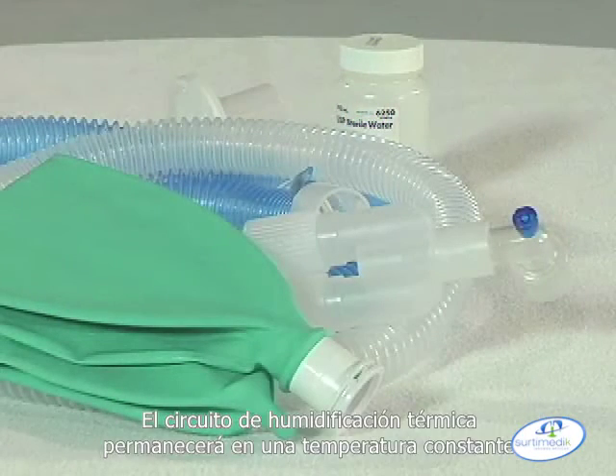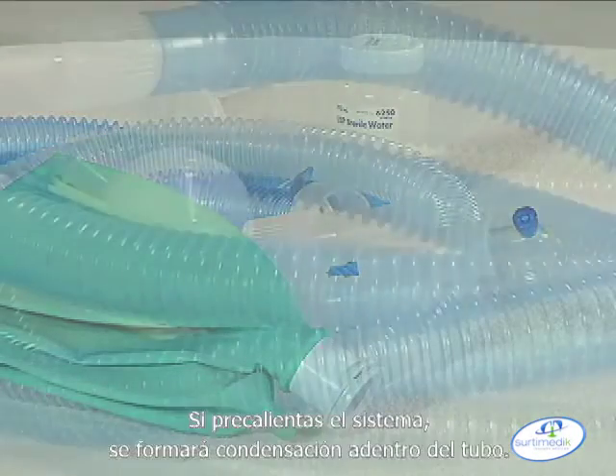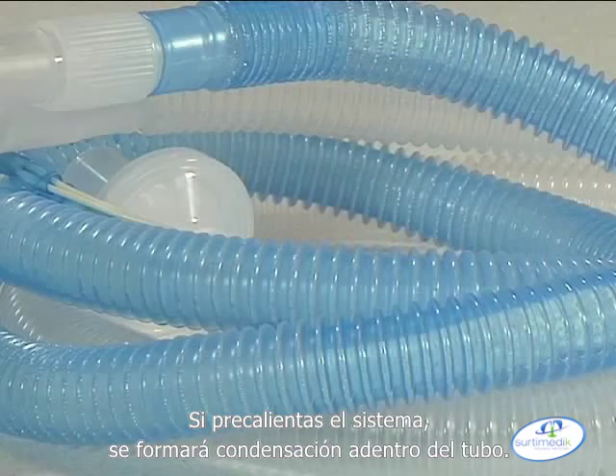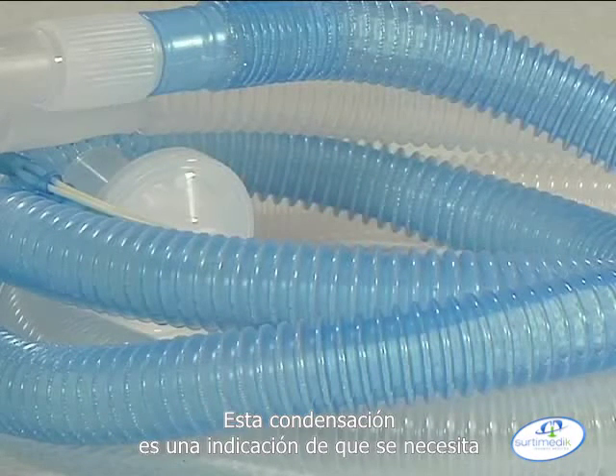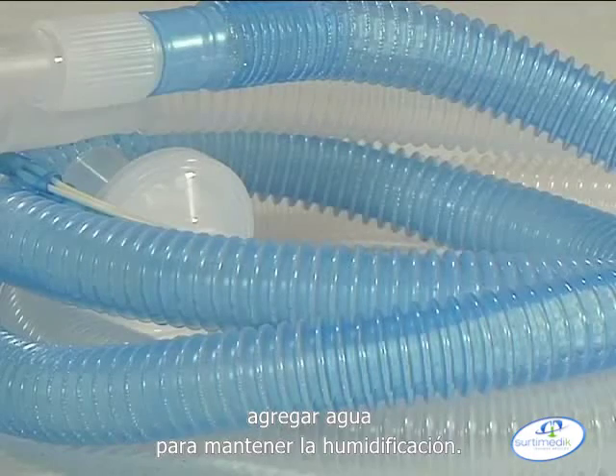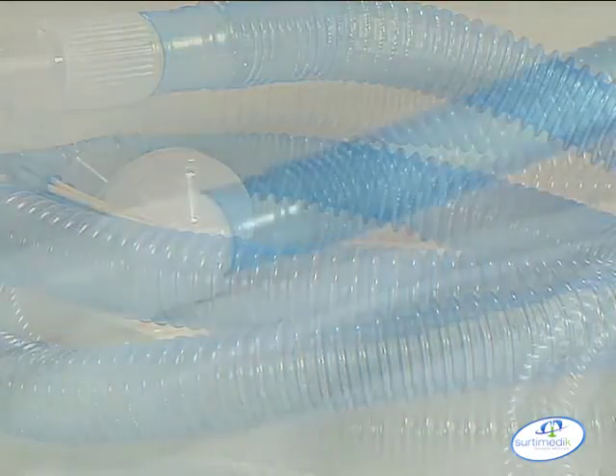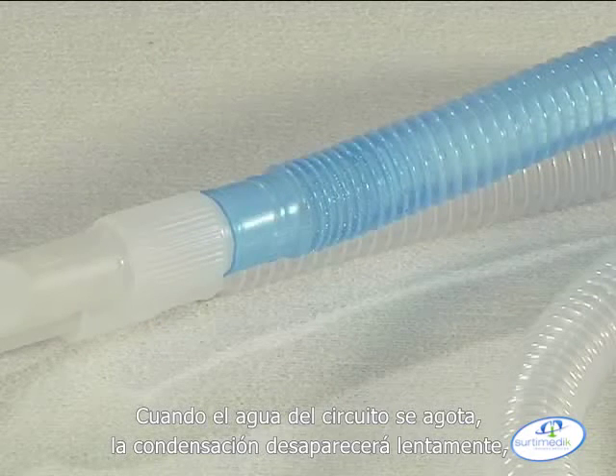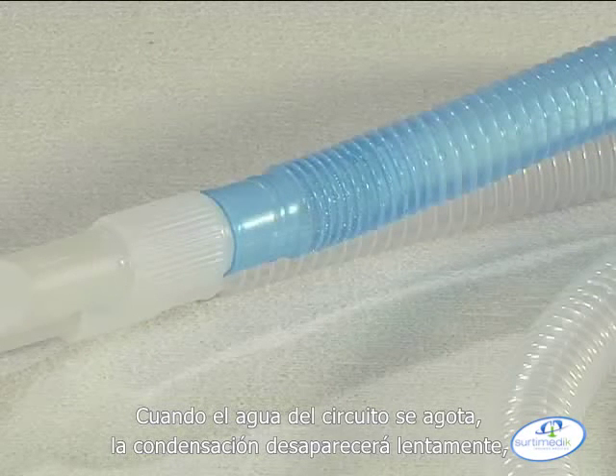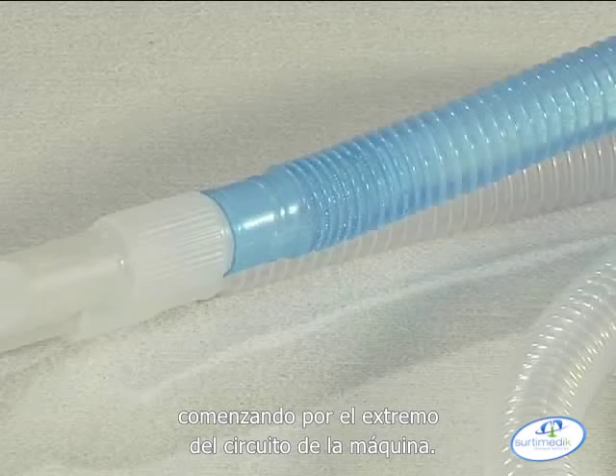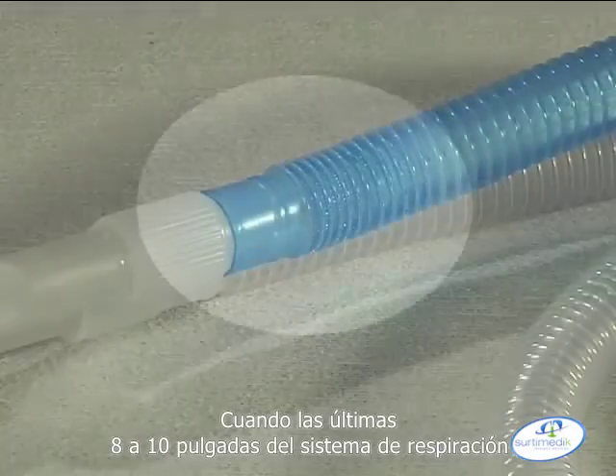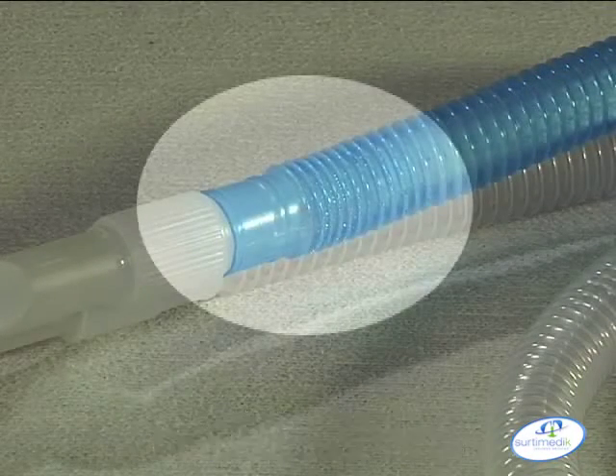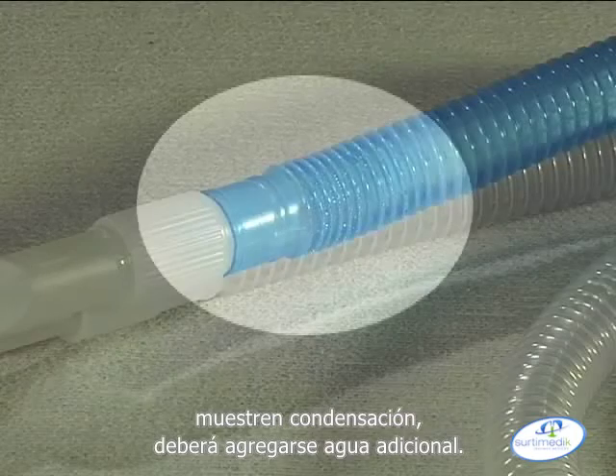Note: the heated wick circuit will remain at a constant temperature regardless of flow. If you preheat the system, condensation will form along the inside of the tubing. This condensation is a gauge or indication of the need to add water to maintain humidification. As the water in the wick circuit is depleted, the condensation will slowly dissipate, beginning at the machine end of the circuit. When the last 8 to 10 inches of the breathing circuit shows condensation, additional water should be added.